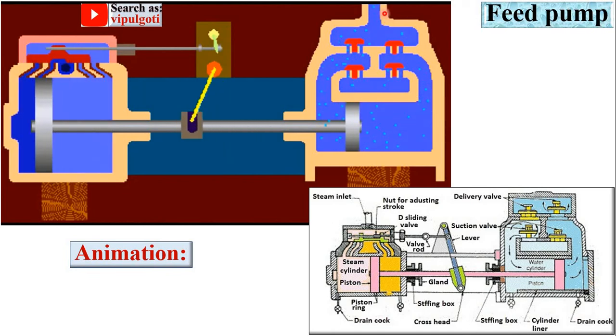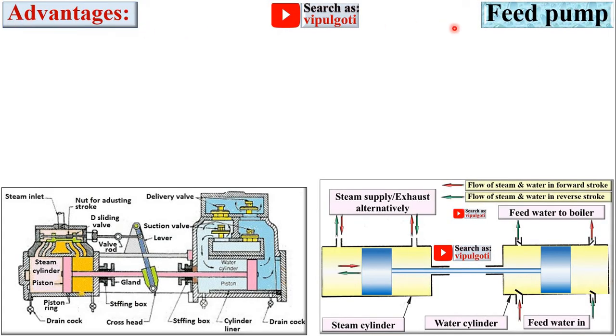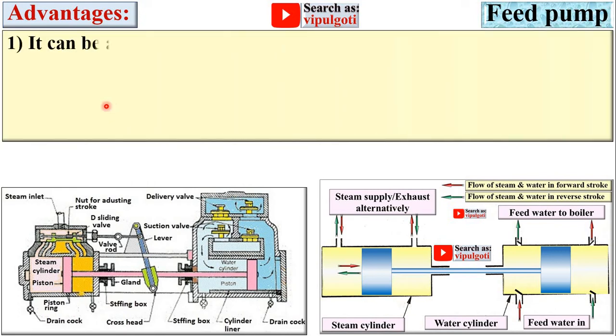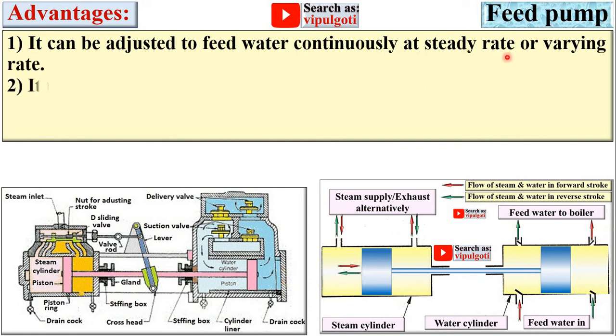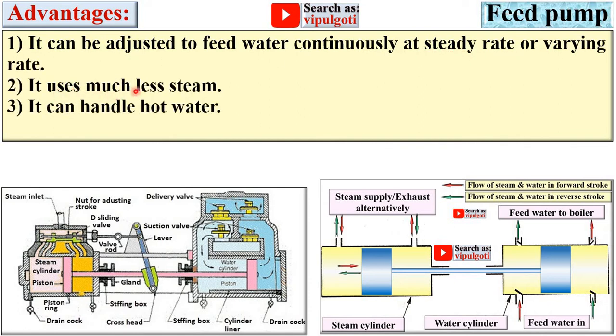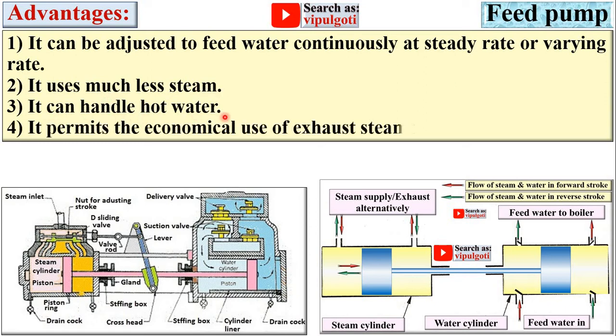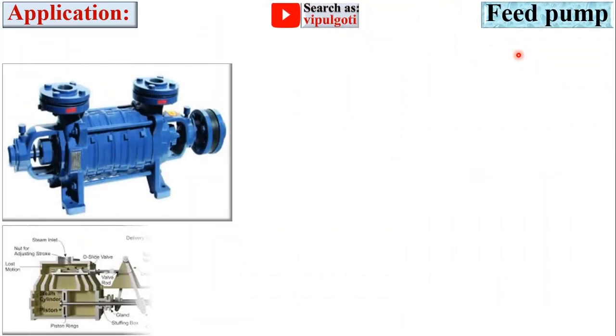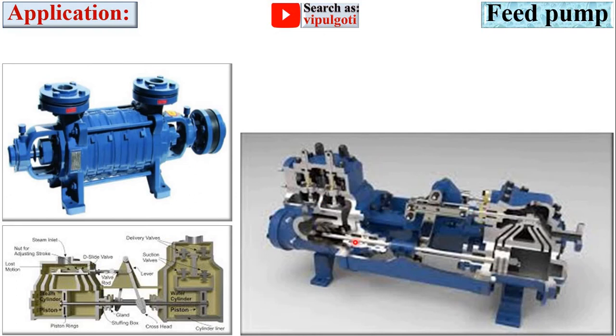Advantages of the feed pump: it can be adjusted to feed water continuously at a steady rate or varying rate; it uses much less steam; it can handle hot water; and it permits the economical use of exhaust steam for feed water heating.